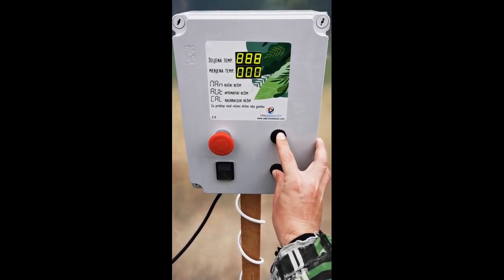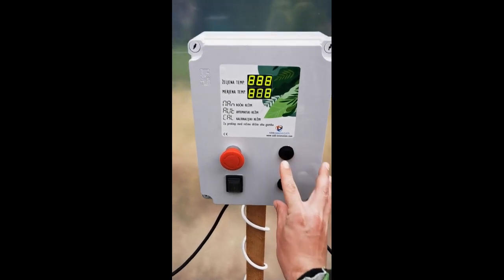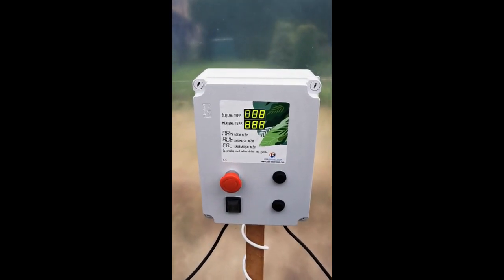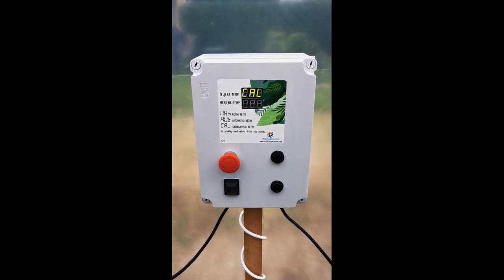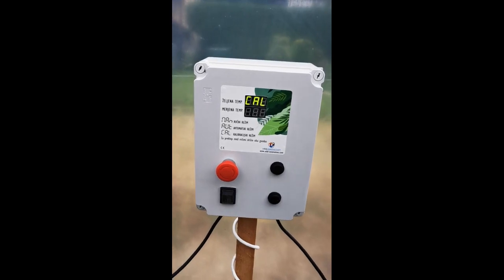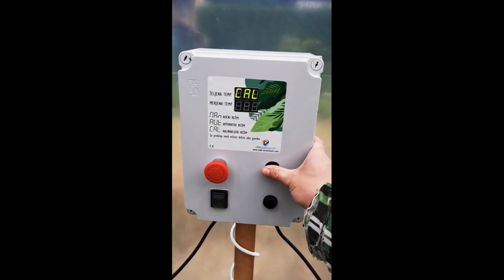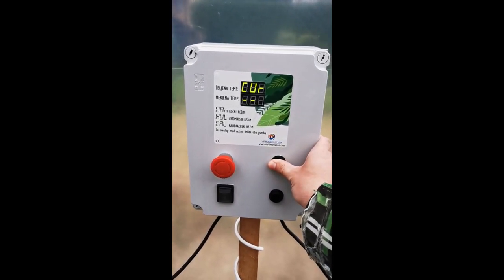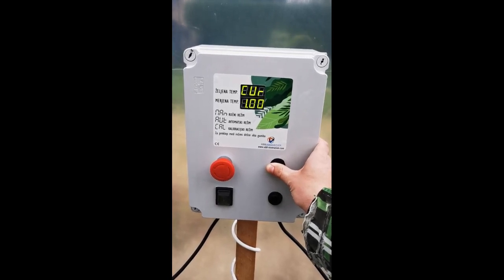3 additional 8s will then appear. When 6 8s are lit on the screen, we can release both buttons. If CAL is displayed in the upper line of the screen, we are in calibration mode. To start the calibration process, hold the button up until 3 lines appear in the bottom line. That's all you have to do.